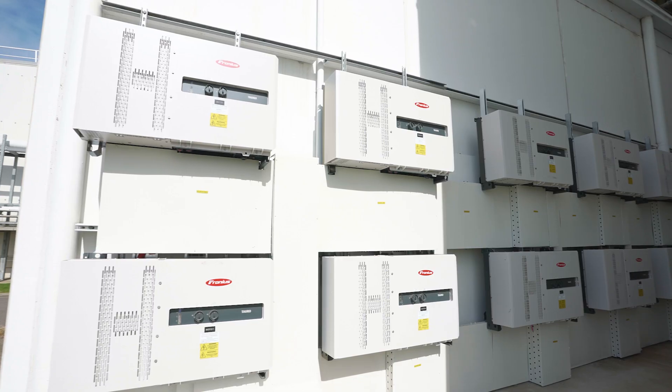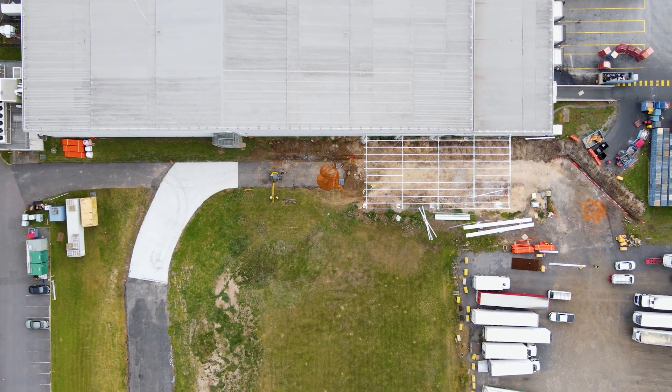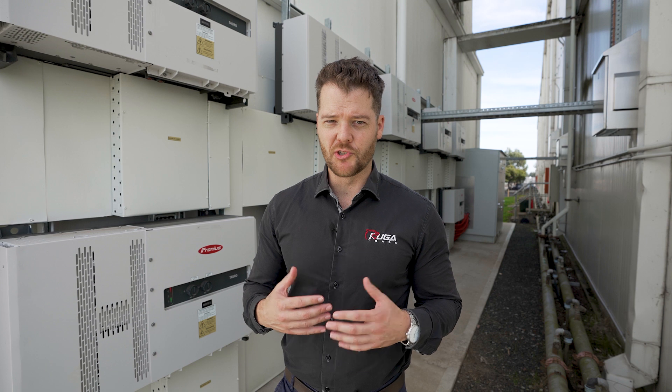Inverter selection was also an important part of this project. Behind me you'll see the 13 Fronius Tauro 100 kilowatt units that we used, and these were selected due to the long DC cable runs. The Tauros are configured in such a way that they allow the DC cable run to be combined, thus reducing the amount of materials and cost on the job.